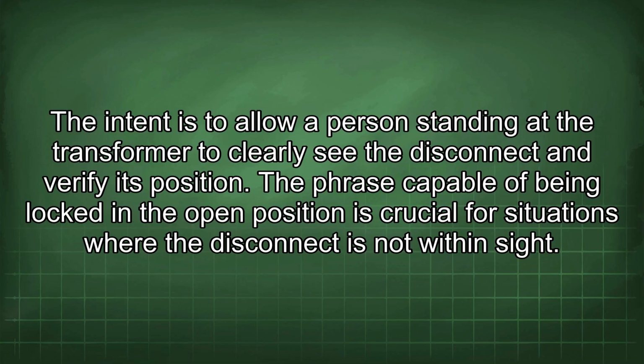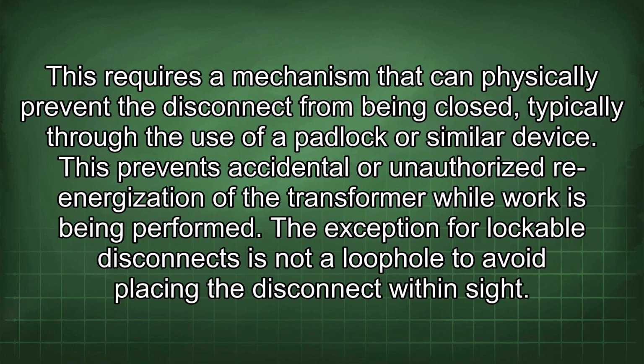The phrase "capable of being locked in the open position" is crucial for situations where the disconnect is not within sight. This requires a mechanism that can physically prevent the disconnect from being closed, typically through the use of a padlock or similar device. This prevents accidental or unauthorized re-energization of the transformer while work is being performed.